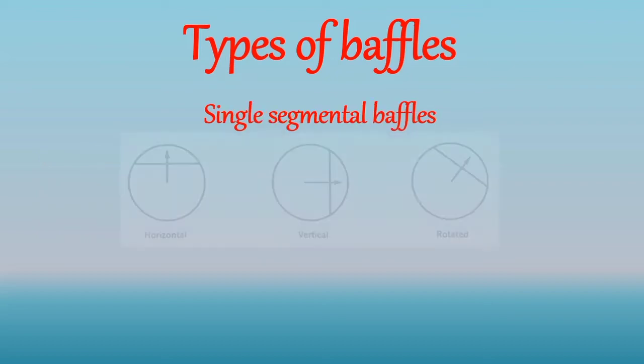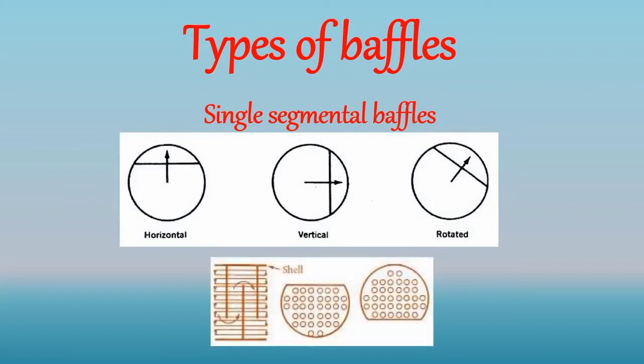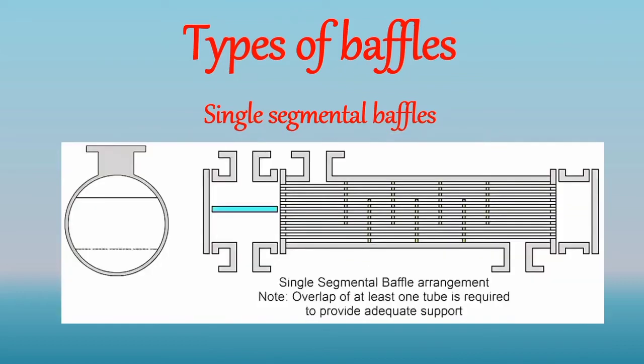The single segmental baffle is mostly used in shell and tube heat exchangers, and it is mostly used in oil refining and chemical engineering devices. The single segmental baffle can be classified into horizontal cut, vertical cut, and rotated cut baffles. When the height of the baffle is 75% of the inside diameter of the shell, it is called a 25% cut segmental baffle. And the 25% cut segmental baffle is the optimum, giving good heat transfer rates without an excessive pressure drop.